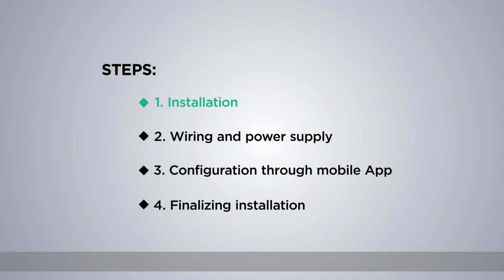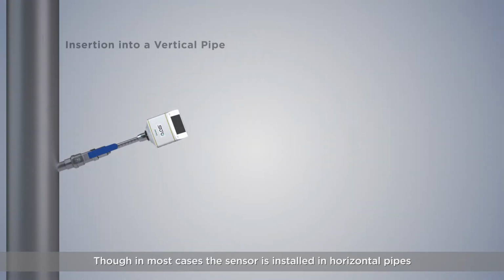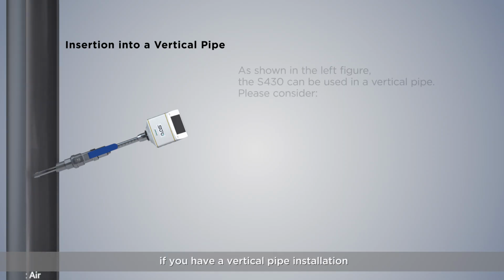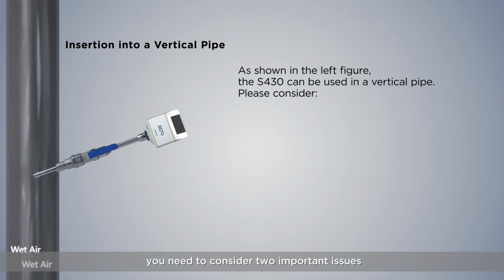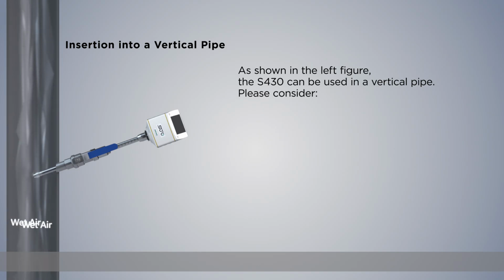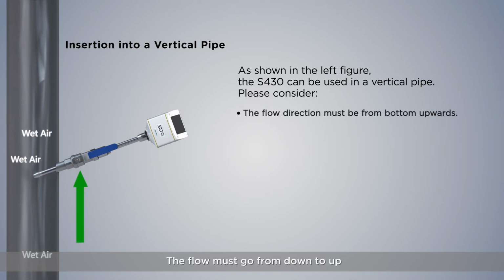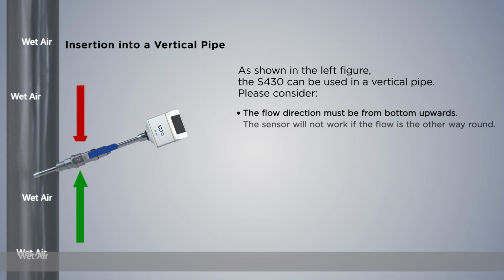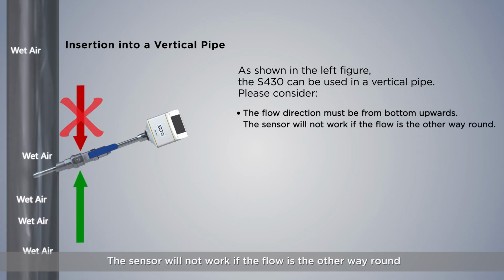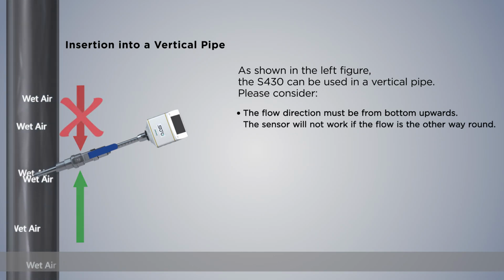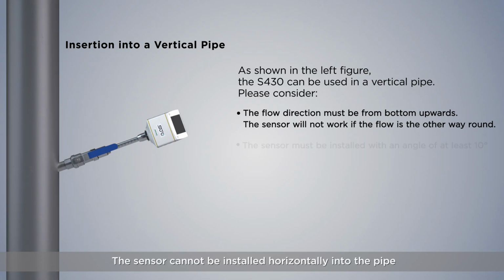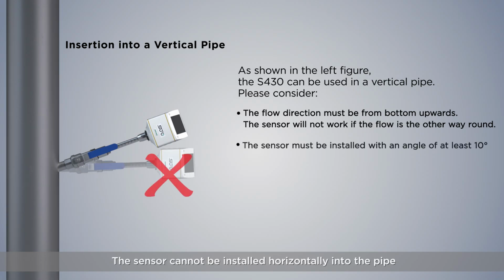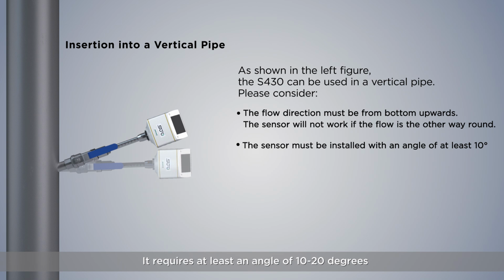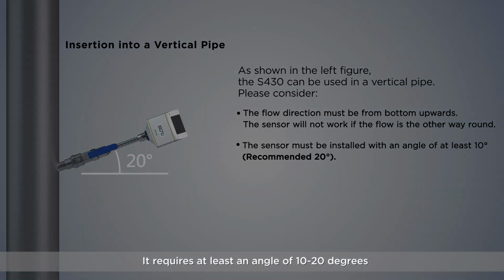Installation. Though in most cases the sensor is installed in horizontal pipes, if you have a vertical pipe installation, you need to consider two important issues. The flow must go from down to up. The sensor will not work if the flow is the other way round. The sensor cannot be installed horizontally into the pipe. It requires at least an angle of 10 to 20 degrees.